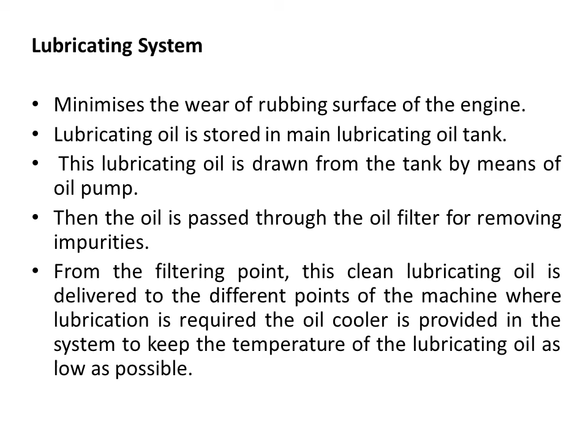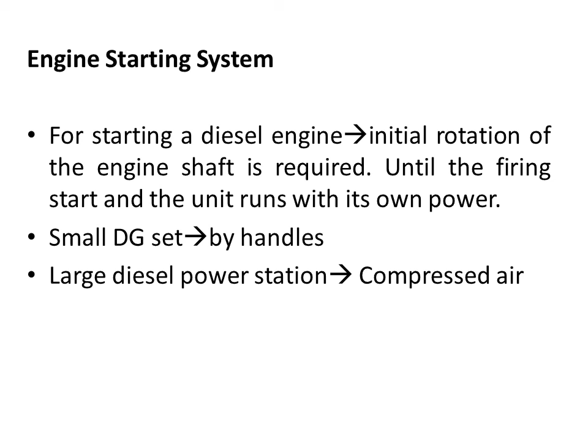Then the engine starting system. Small diesel power stations can be started manually for their initial starting, but large diesel power generating stations with large diesel sets cannot be started by manual methods. In that case, compressed air is used for starting. For starting a diesel engine, initial rotation of the engine shaft is required until firing starts and the unit runs with its own power. For small DG sets, initial rotation of the shaft is provided by handles or manually, but for large diesel power stations, compressed air is used for starting.